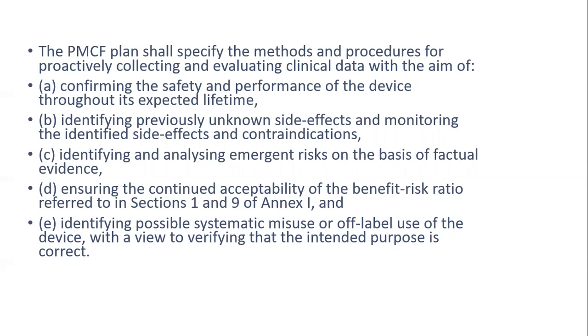Identify and analyze emergent risks on the basis of factual evidence. Ensure the continued acceptability of the benefit-risk ratio. The benefit-risk ratio is very important. You have to mitigate all the risks in the risk file as far as possible, and the benefit should outweigh the risk available in the risk management file. Identify possible systematic misuse or off-label use of the device with a view to verify the intended purpose is correct. These are the different objectives in a PMCF plan that we look for.